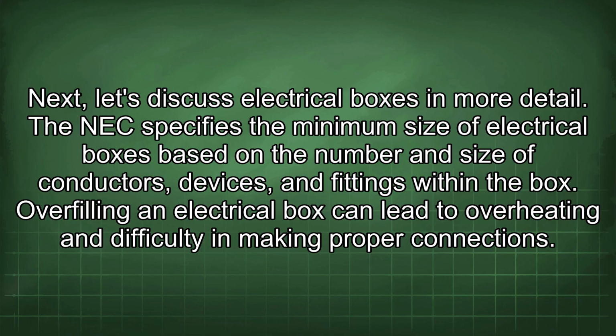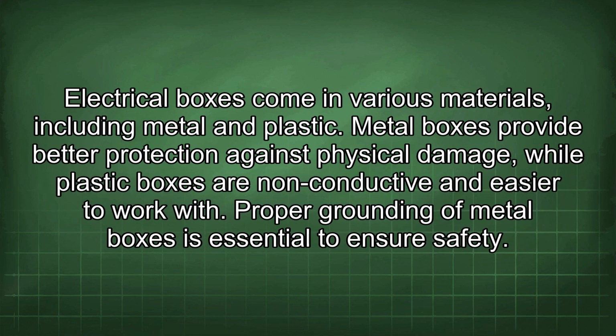Next, let's discuss electrical boxes in more detail. The NEC specifies the minimum size of electrical boxes based on the number and size of conductors, devices, and fittings within the box. Overfilling an electrical box can lead to overheating and difficulty in making proper connections. Electrical boxes come in various materials, including metal and plastic. Metal boxes provide better protection against physical damage, while plastic boxes are non-conductive and easier to work with. Proper grounding of metal boxes is essential to ensure safety.